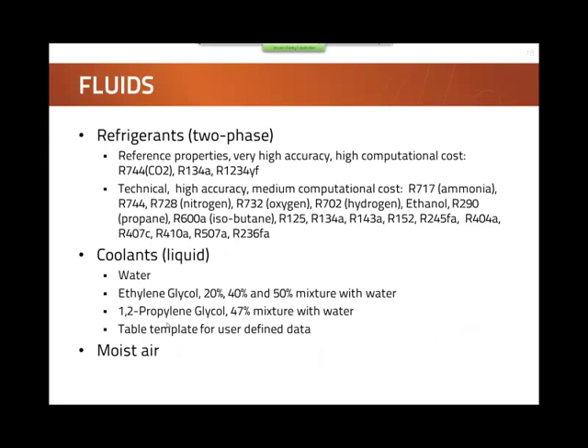There is a wide range of fluids supported by this library. For refrigerants, besides those typical for air conditioning applications like R134A, there is the newer refrigerant R1234YF and CO2. There are many more typically used in household refrigeration, supermarket refrigeration, or heat pumps. On the coolant side — single-phase liquid — we have ethylene glycol-water mixtures, pure water, and propylene glycol mixtures, and you can also specify your own medium. Moist air is used on the air side, so humidity and condensation in evaporators are always taken into account.